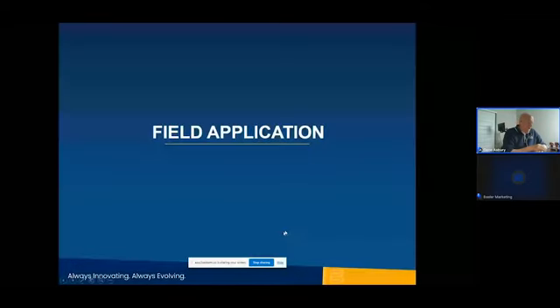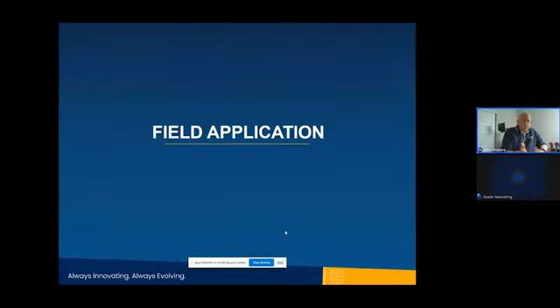So let's talk about the field application for now. I'm going to talk about two different types of synchronous motor. Mostly I'm going to talk about the brushless excited motor, but right now I want to talk about slip ring motors. The difference is you don't have a rotating exciter on the motors. You're basically using an independent DC power source to excite the field of the motor itself.